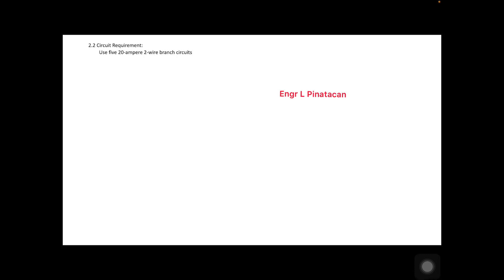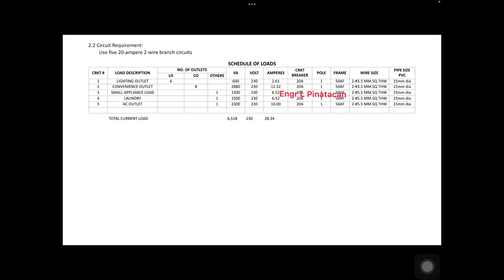The circuit requirements call for five 20-ampere two-wire branch circuits: circuit 1 for lighting outlets, circuit 2 for convenience outlets, circuit 3 for small appliance loads such as a refrigerator and microwave oven, circuit 4 for the laundry machine, and circuit 5 for the air conditioning outlet. The total apparent power on the schedule of load is 6,518 volt-amperes.